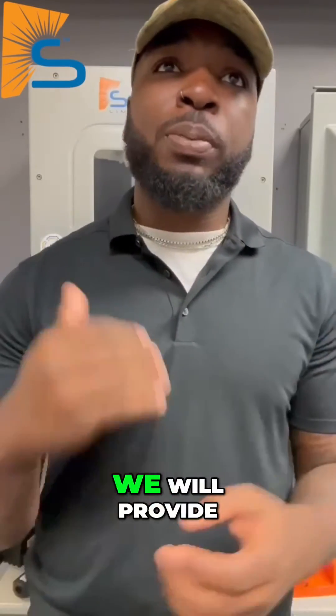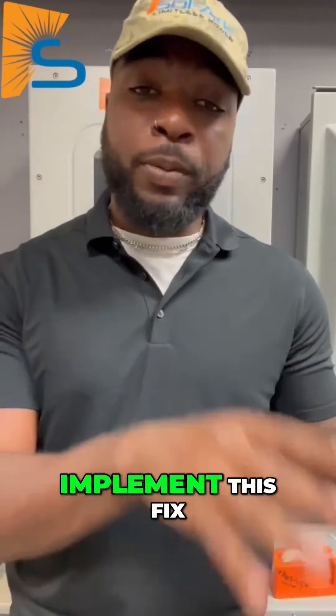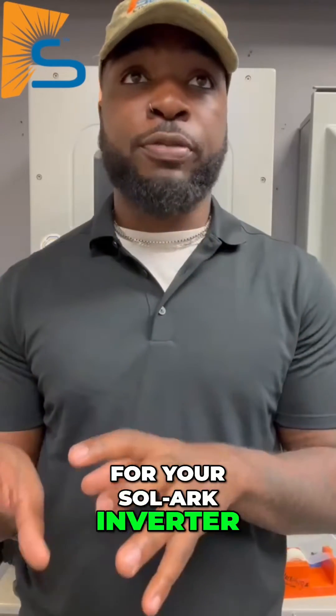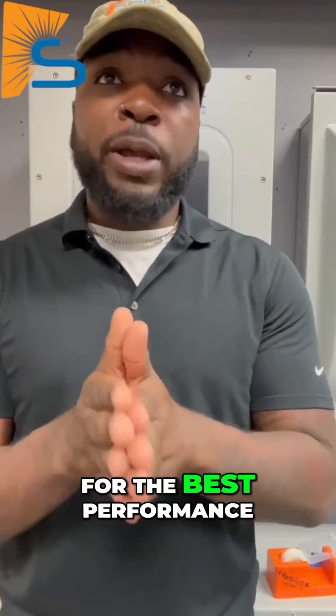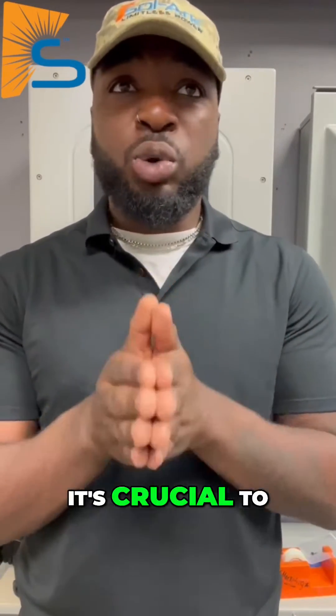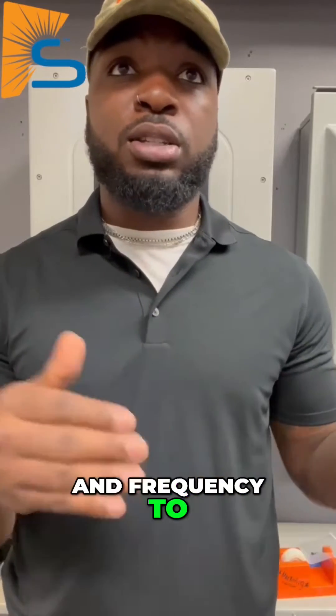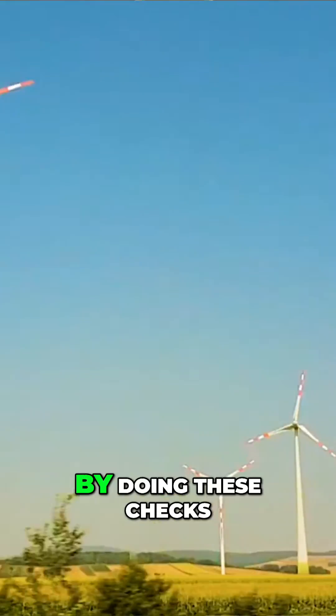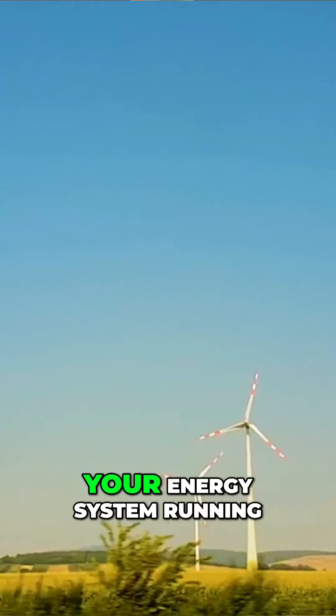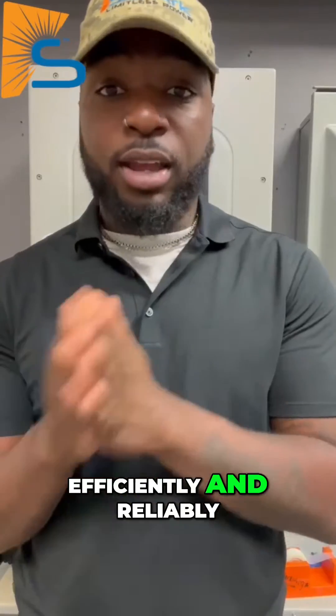By following this simple tip, we'll provide you with the instructions on how to implement this fix for your Sol-Ark inverter. First, you're going to want to check your voltage and frequency. For the best performance of your Sol-Ark inverter, it's crucial to regularly check the grid's voltage and frequency to ensure they match your inverter's settings. If they don't align, your system might not connect to the grid properly. By doing these checks, you'll keep your energy system running efficiently and reliably.